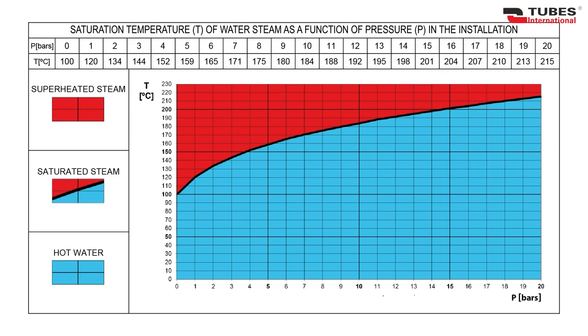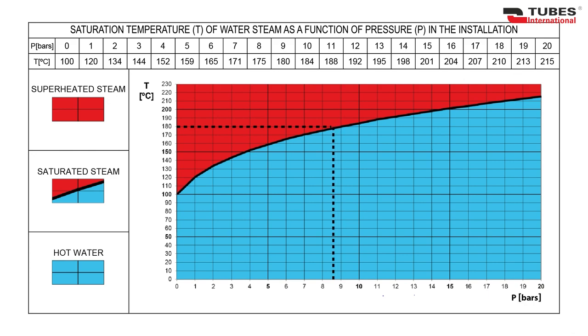Rubber steam hoses are designed to conduct saturated steam. When steam is concerned, temperature and pressure are closely related. On the graph, the x-axis is pressure and the y-axis is temperature. At 180 degrees Celsius and a pressure of 9 bar we get saturated steam, which is what we are interested in. But when one of these values changes — for example when a valve in a system suddenly opens and the pressure drops — our saturated steam turns into superheated steam.